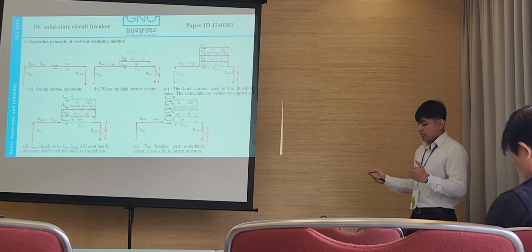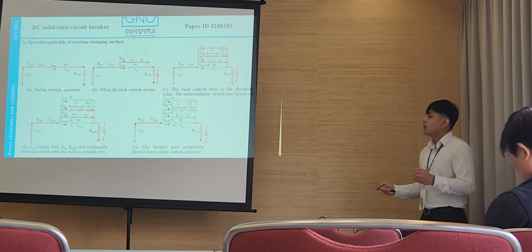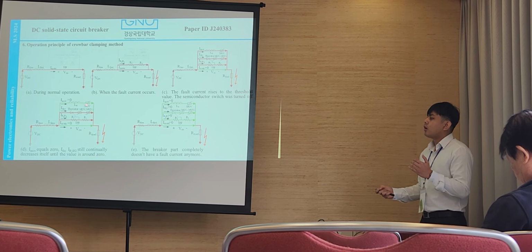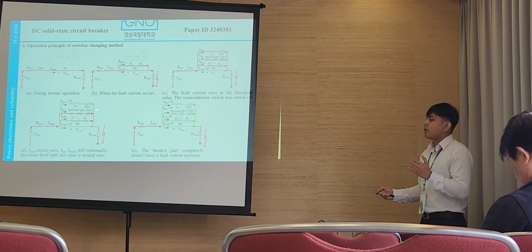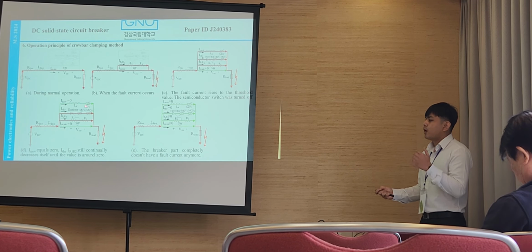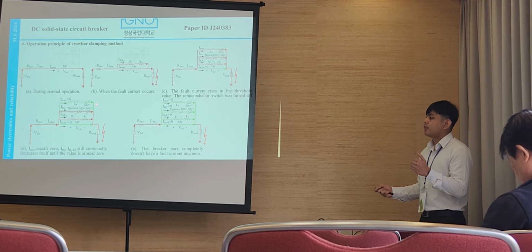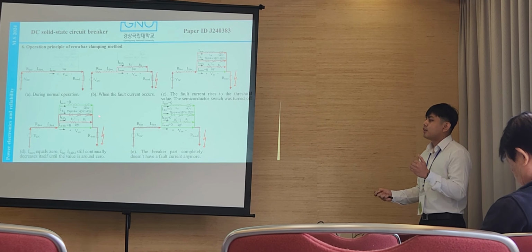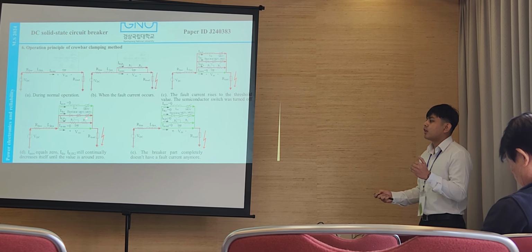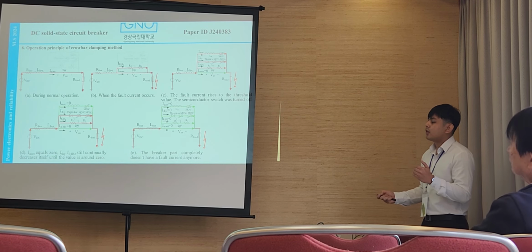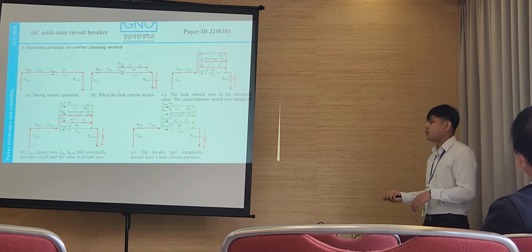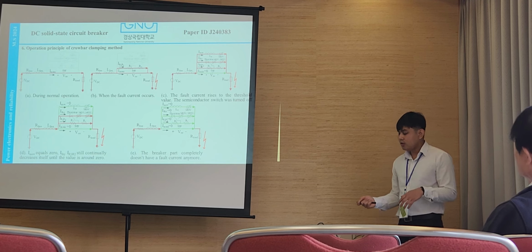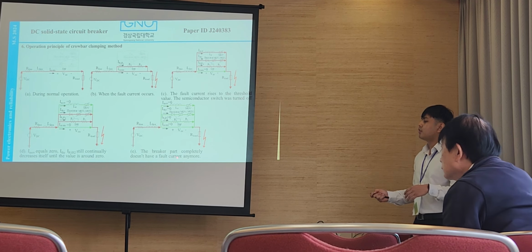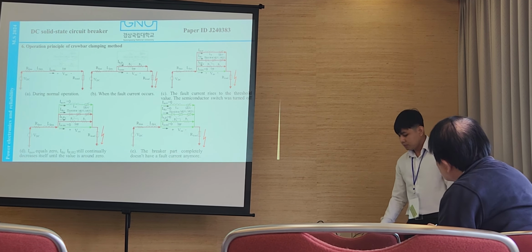For D, the original MOV branch will have a current that oscillates and disappears in a very short time. After that, only the transistor branch and voltage divider branch continue to decrease until the value reaches zero. Finally, the breaker path completely has no fault current anymore.